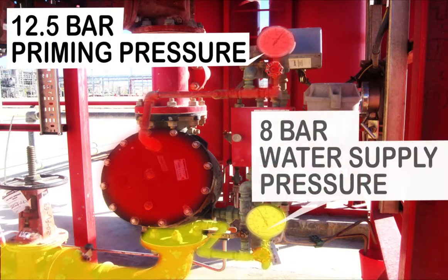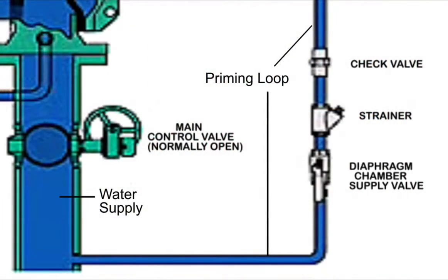However, the priming chamber here indicates a higher pressure, which is common to all the deluge skids present on site. This could be explained by the presence of a check valve before the priming chamber. When the pressure of the fire water ring rises, the water supply pressure rises, causing the priming pressure to rise. When the pressure in the fire water ring falls again, the priming pressure remains high, due to the presence of the check valve which prevents the priming pressure from falling.